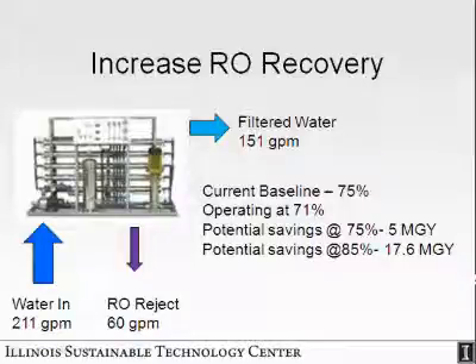But the way that the system is operated, they are only operating at 71% recovery, as opposed to the design level of 75% recovery, and therefore it just requires a change in the operational practice for them to be able to bump up this recovery rate from 71% to 75%. If you did that, and there is really no reason why they can't do that, it is only a question of operational control and monitoring of the system, then you can save about 5 million gallons per year.